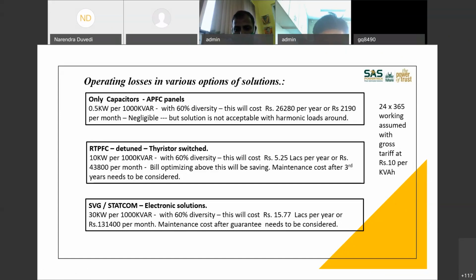Now, this 30 kilowatt loss, if it is happening in your LT room, obviously they might ask you to put an air conditioner for a better working of this panel and better output available from this panel. So again, that air conditioner consumption also you have to add back. I have not added that. Even without that air conditioner, the 1000 kVAr panel will consume about 1,31,400 rupees worth of energy per month. So you have to take it out from whatever you are going to save out of this, and then calculate what payback you will get by adding this.